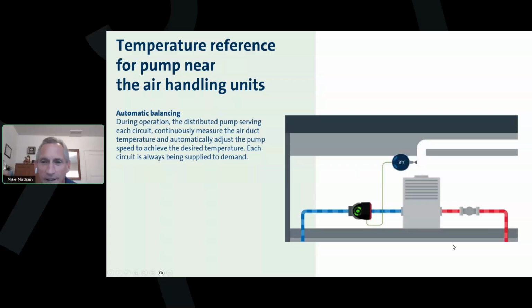Yes. So in our early days, we showed the pump like this. We showed it on the supply side and the check valve here. My pump has a built-in temperature sensor. It has built-in flow estimation. And so more often today, we're saying, let's put the pump over here on the return side, between the air handler and the check valve, because that gives me a real benefit. I know what my supply water temperature is already. My pump has a built-in temperature sensor, so I'll know what my return water temperature is. And I have flow estimation. So now, by putting it on the return, I have BTU information for every air handler, and I can send that back to the BMS system. So it's great for diagnostics. When you start seeing some new slides from me, maybe next time you see this or a similar presentation, you'll actually see the pump on the other side, over here.